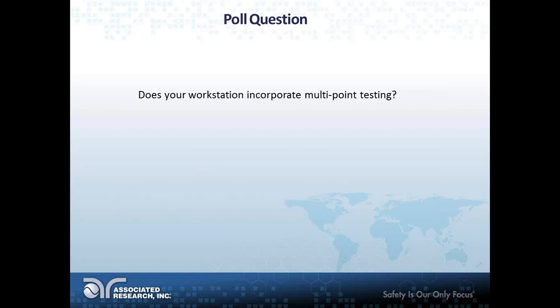Okay, so before we go into the real meat of this webinar, which is multi-point testing and automation, we'd like to do a quick poll. All of the tests that we have talked about in the past and just now in this webinar are required to be performed at multiple different points on a product, especially when it comes to medical device testing. There are many patient connections, patient leads, and applied parts that are required to be tested for all of the tests that we talked about, and that's why the need for multi-point testing comes in.